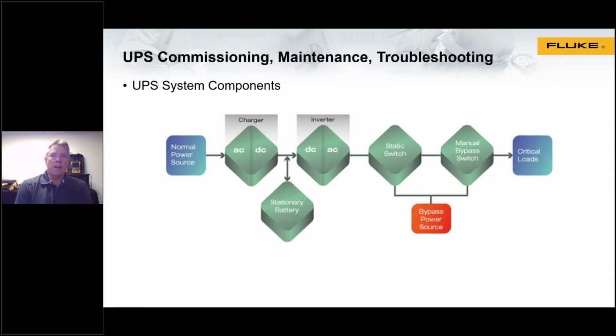UPS system itself. Again, keep in mind it's for commissioning, maintenance, and troubleshooting. That's a typical block diagram of a UPS system where you have your normal power source coming in, providing power to a charger, which can charge the stationary batteries for backup. And then you have an inverter on the output side of that to convert back to AC, which would go through static and manual bypass switch or some other bypass power source if need be, such as a standby generator, all there to power your critical loads.